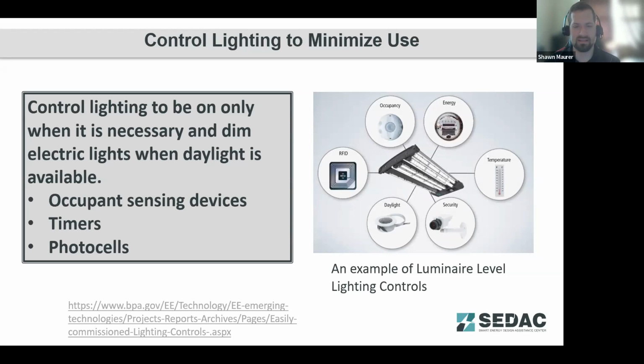And then also making these as simple as possible. The more sensors you have in the space, the more controls you have, the greater the maintenance load is going to be on the building, and the more likely it is that over time you're going to lose the operational efficiency of that system. So kind of looking at the luminaire level lighting controls, you've got some built-in capability there for space modularity, but again, you've got more sensors, more things that can break down over time and result in long-term loss of efficiency. So there's a bit of a trade-off there. Making sure you're aware of those in your design process is a key element to efficient design.